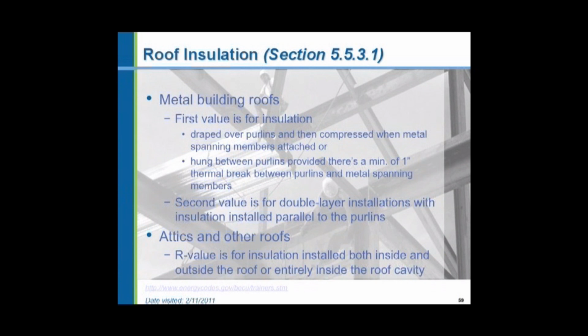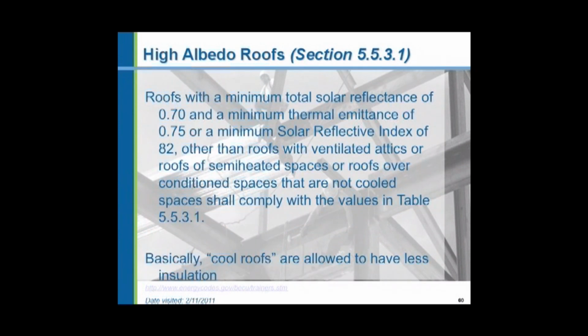For metal buildings, they're talking about draping the insulation one direction over the purlins, then another layer of insulation crossways, parallel to the purlins, and then having spacers at least 1 inch thick that space the metal roofing off the insulation so it doesn't get squashed to nothing where the roofing is screwed down to the purlins. Now they have what they call a high albedo roof, and that's basically a light colored reflective roof that reflects the sunlight. It's a cool roof, and they allow you to put less insulation in the attic or under a cool roof.